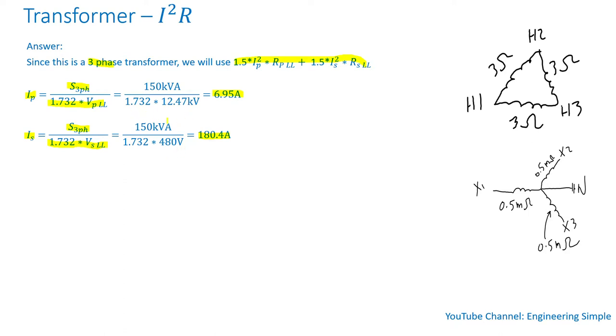Note that the side with the highest voltage has the lowest current, and the side with the lowest voltage has the highest current. Always check that your numbers make sense — for example, if you calculated 300 amps on the high-voltage side, that should be a flag that something is wrong.